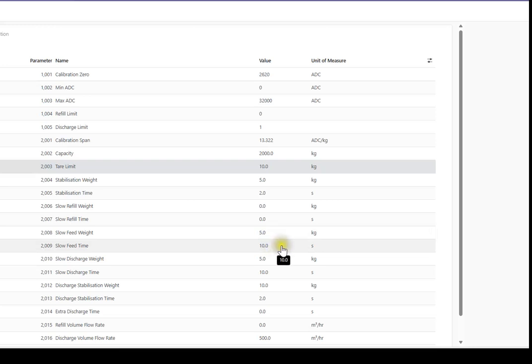Now on normal weighing in scales, the feeder that feeds material into the weigher will continue. But on a liquids weigher, it's quite often a pump and things, so there could be problems. On a liquids weigher, it would normally stop and let the operator retry it. I jumped over 2 values here, refill, but this is not a refilling weigher, so they are not used. Discharge weight is the same thing. When the weight gets below the tare limit, as long as it doesn't move by more than 5 kilograms in 10 seconds, then it's discharging. The stabilization weight means it's got to stay within 10 kilos for 2 seconds on discharge.